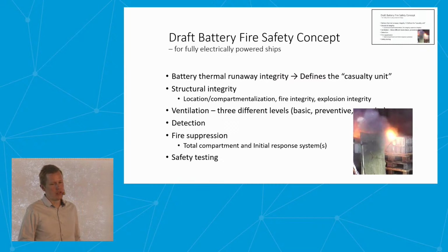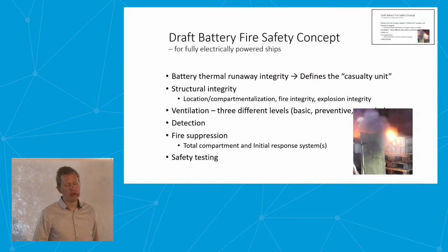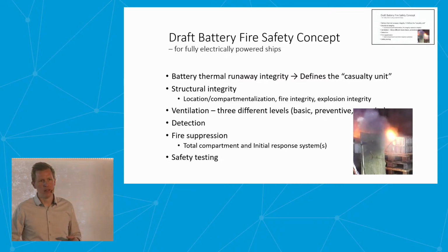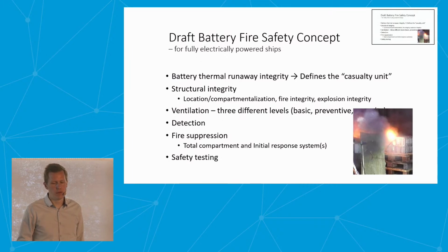Based on that, you could say, is your design safety level. Based on this unit, you could also design your ventilation system, explosion integrity, and so on. The structural integrity also includes location of the battery compartment, backup power, compartmentalization, redundancy of the battery rooms, ventilation, detection, of course fire suppression, and testing.